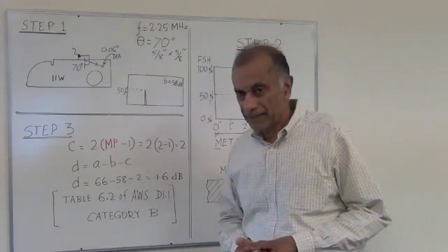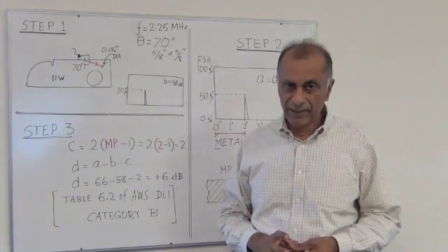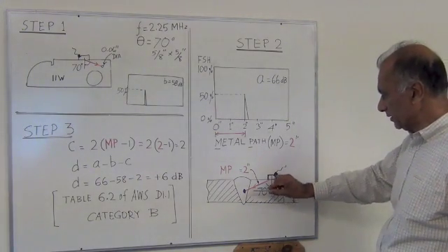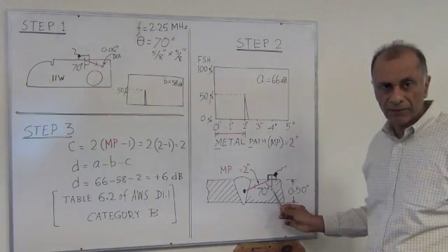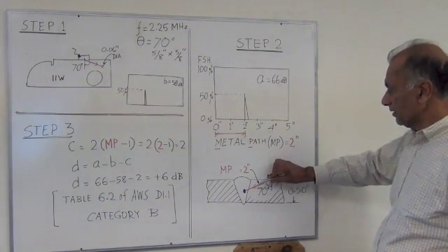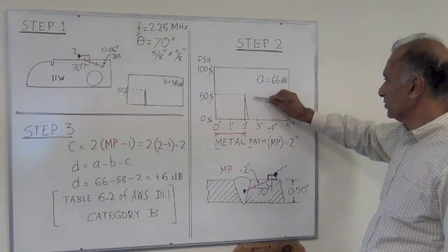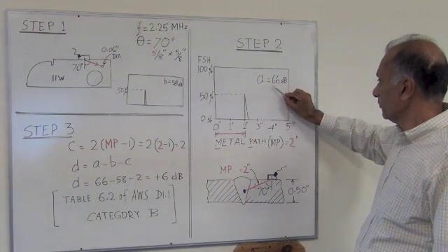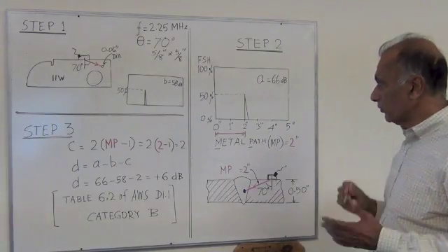Then we start scanning the structure. Let's say we find an indication while we are scanning. Here we are doing the inspection, and this is the indication in purple color, same probe, 70 degree probe. Then again we adjust the signal from this indication to 50%, and in this case this is called gain indication rating A.